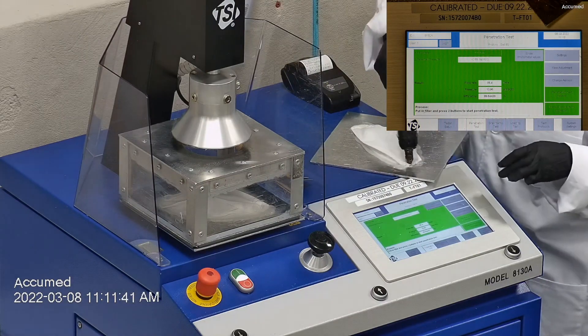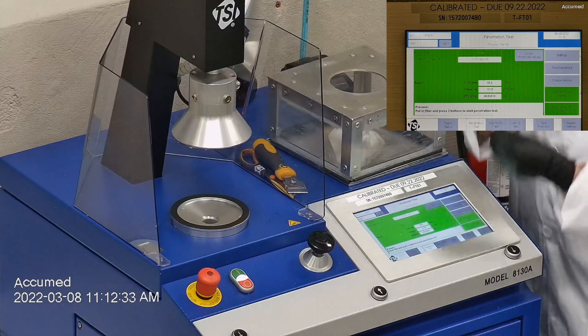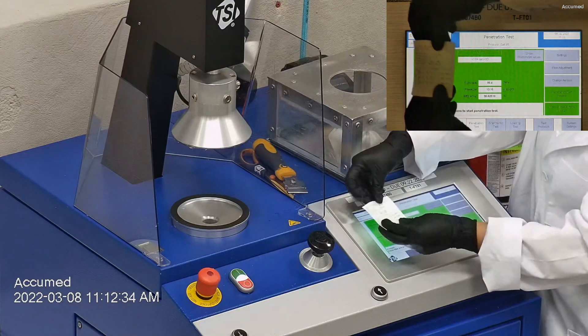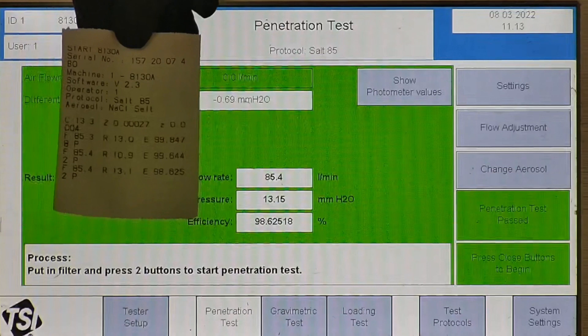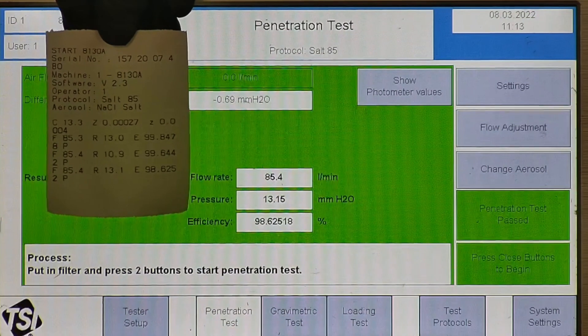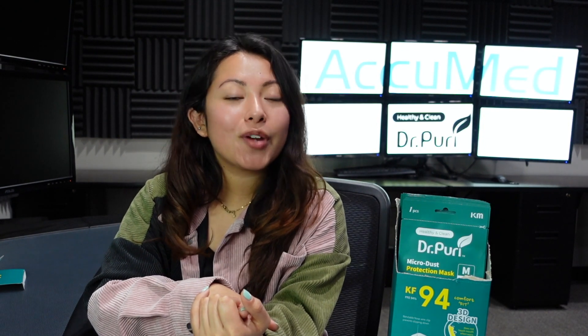Now let's go over the results. F stands for air flow rate, which we test at 85 liters per minute. R is for resistance, also referred to as pressure drop — this correlates with breathability, so the lower the number, the more comfortable and breathable the mask. E stands for filtration efficiency percentage. The filtration percentage for all three masks came in at 98.63% and above. All three results were 98.62% or above, so they did pass the filtration test.